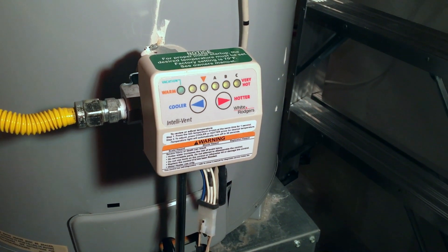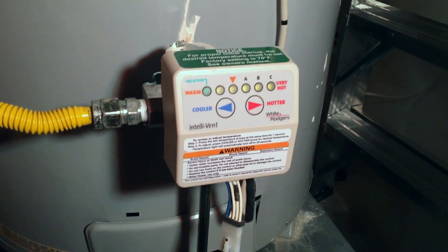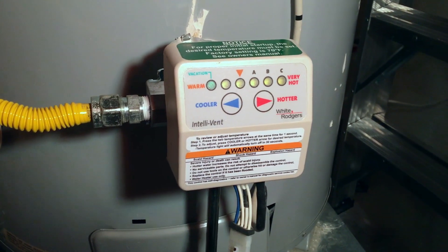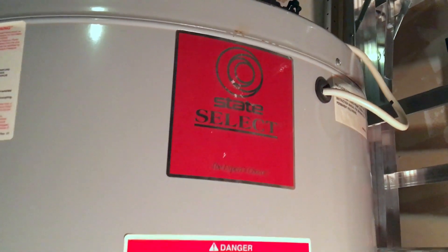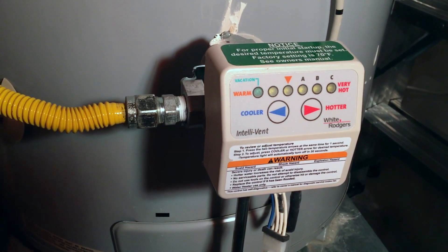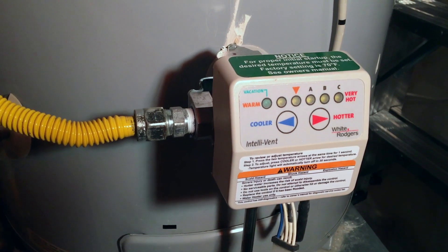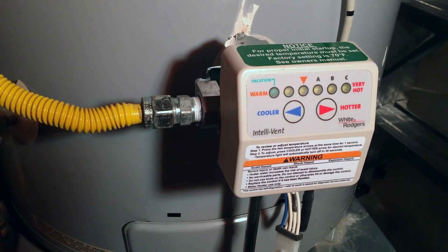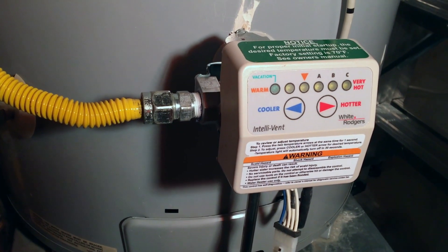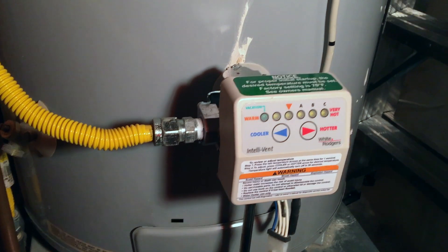I'm going to go through the troubleshooting steps I used when I had a unique problem on my water heater. This is a White-Rodgers Intelli-Vent module, and it's a State Select water heater - but really the brand doesn't matter much. What matters is how the ignition works. This has an ignition rod with a flame sensor, so it's not a traditional pilot light water heater. It's a newer type - pretty much all of them are this way now, so you don't have a little pilot light burning gas all the time.